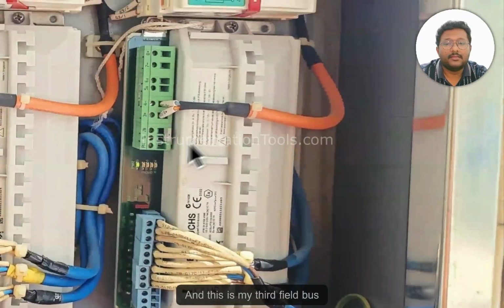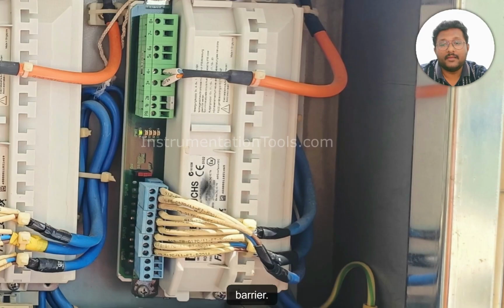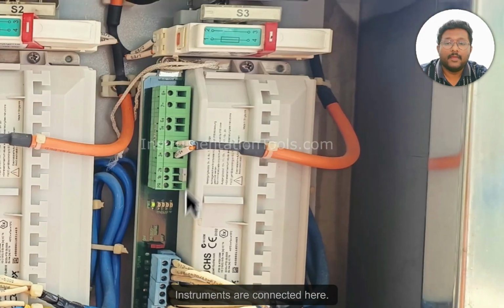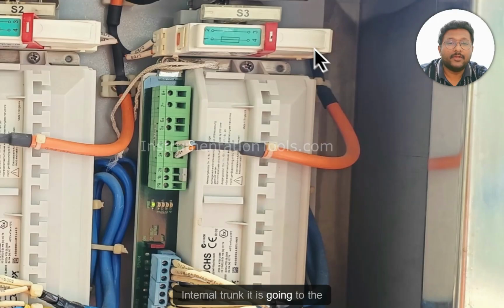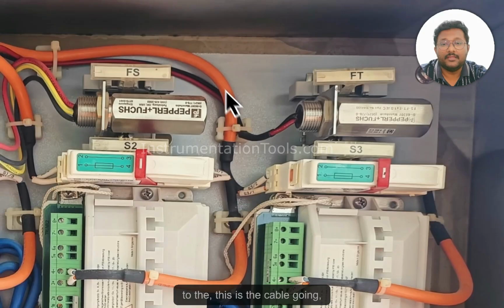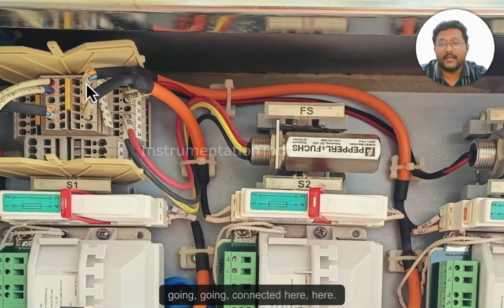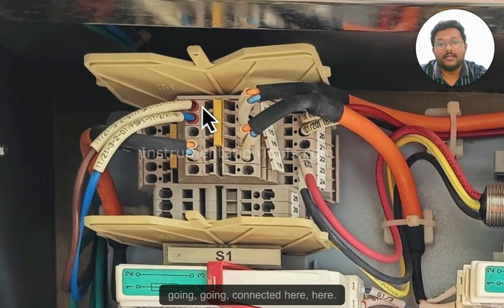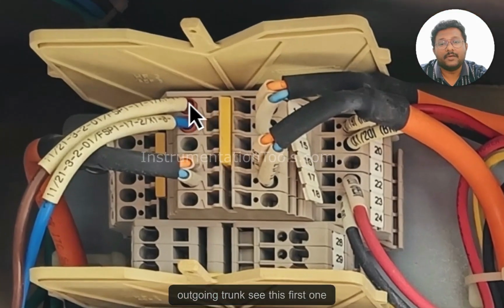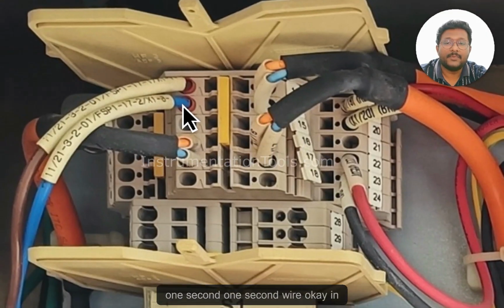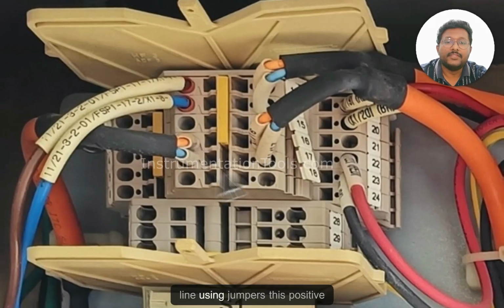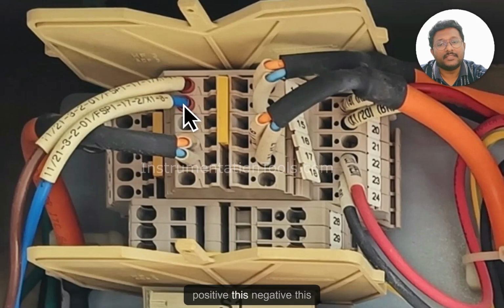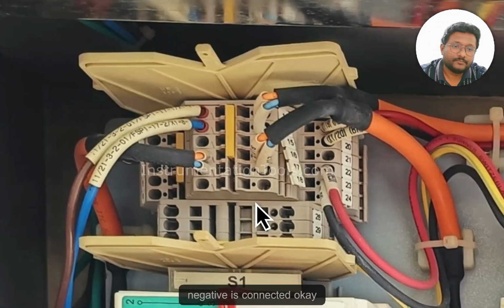And this is my third field bus barrier. Instruments are connected here. Internal trunk, it is going to the isolation switch, this is the cable going and connected here. And this is my external trunk, outgoing trunk. See, this first one and this first one are in line, the second wire also in line. Using jumpers, this positive is connected to this positive, this negative is connected. Okay.